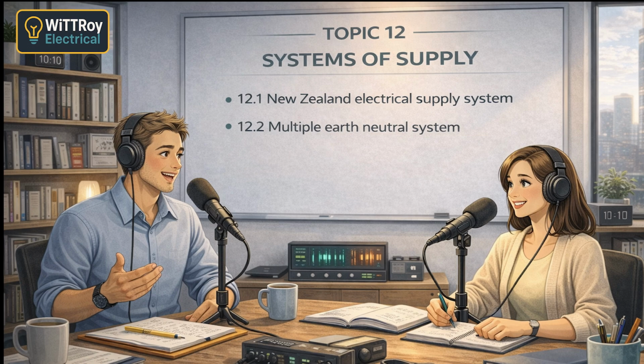MEN stands for Multiple Earth Neutral. The neutral is connected to Earth at the distribution transformer and again at the main switchboard through the MEN link. So that link joins the neutral bar and the earth bar. Correct. This keeps the neutral close to Earth potential and provides a low resistance path for fault current. So protective devices can trip quickly. Exactly. That's the whole safety purpose.